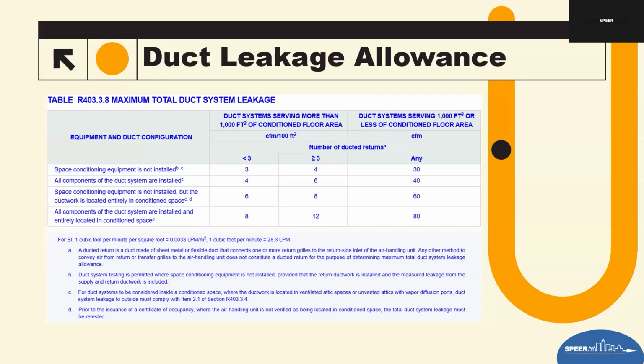So if there are ducted returns, fewer than 3 or 3 or more, more returns mean more potential leak pathways and a slightly higher allowance. So instead of 4 CFM, as we see here, and this was surprising to me, and I understand why they did this, we could potentially be going up to even higher than that because of the number of returns and size of the home. Then on the second column, to the right, small systems have a really hard time getting down to 4 CFM per 100 square feet.